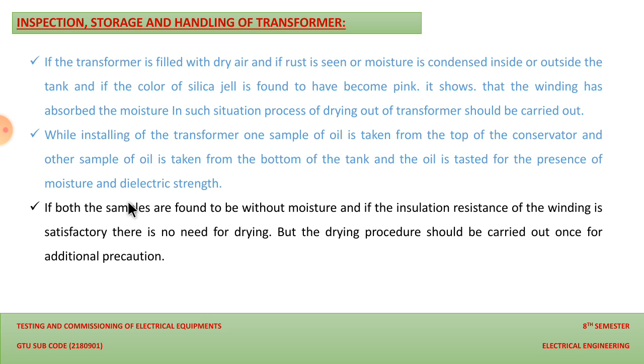So dielectric strength is required, because dielectric is nothing but the insulation between the windings and the conducting parts which are present inside the transformer. And if moisture is present, or the dielectric strength is not proper, then we cannot use this transformer. So that's why we have to take samples of oil to check the dielectric strength of the oil which we are using inside the transformer. If both the samples are found to be without moisture, and the insulation resistance of the winding is satisfactory, there is no need for drying out.